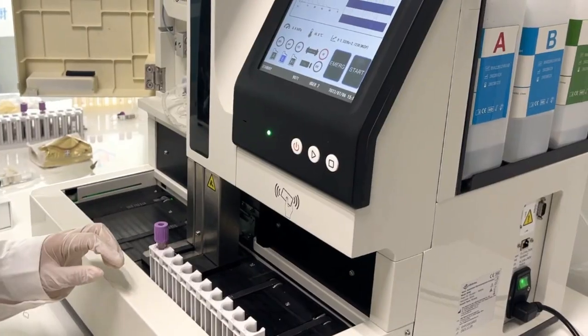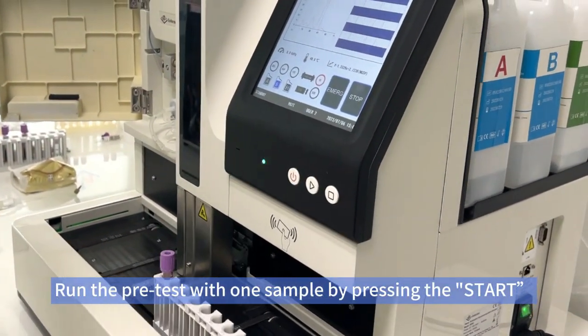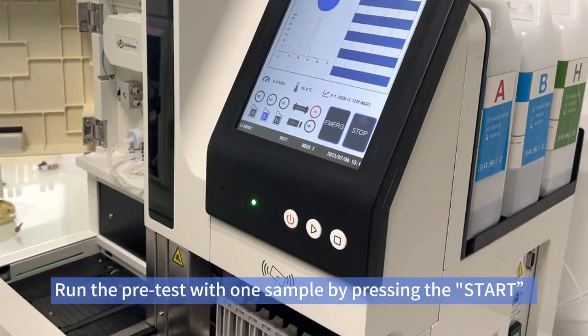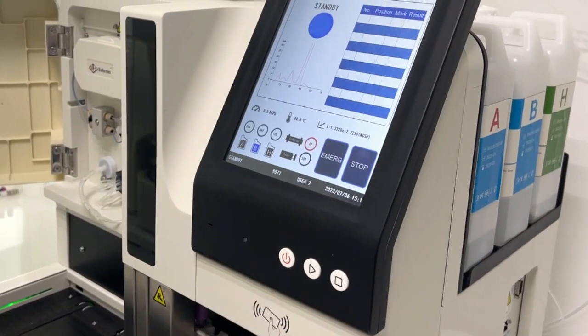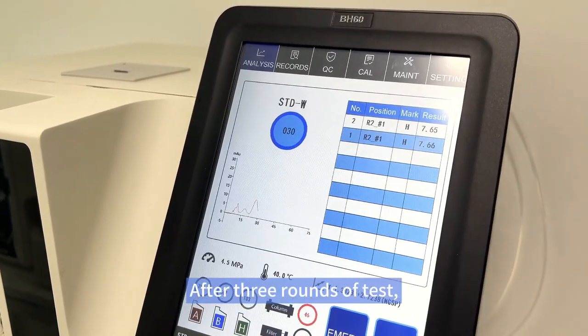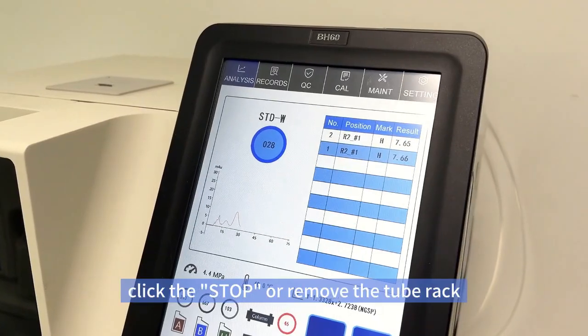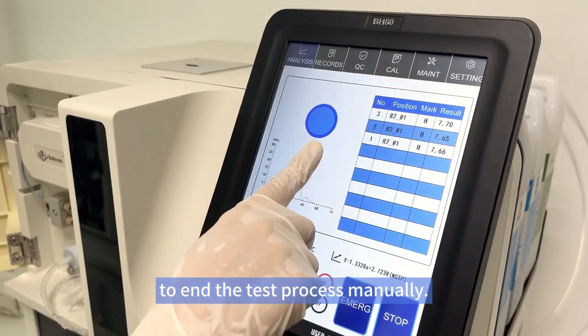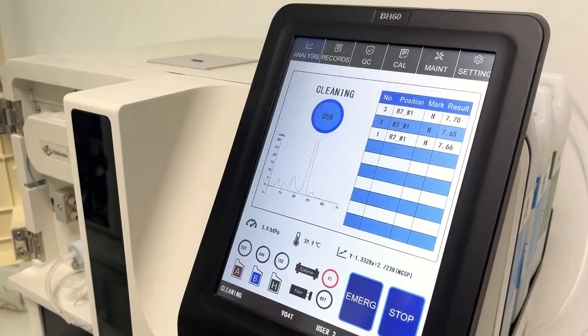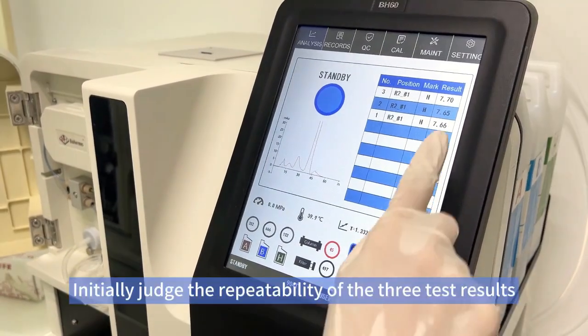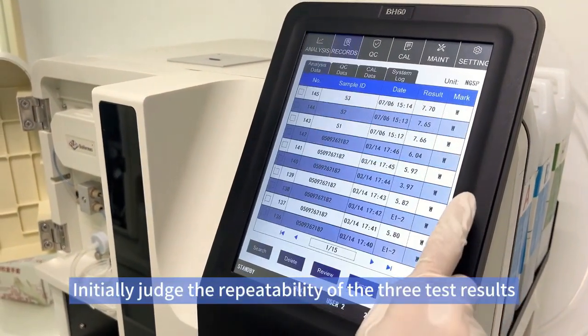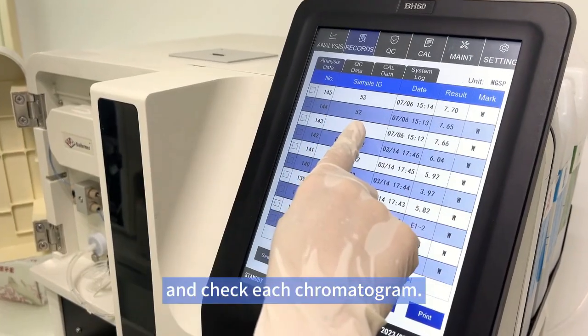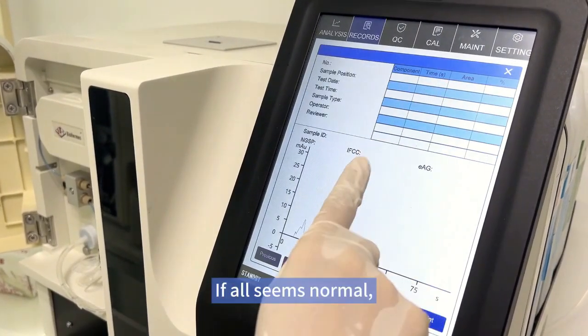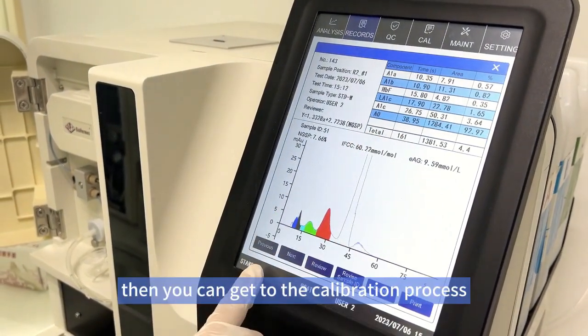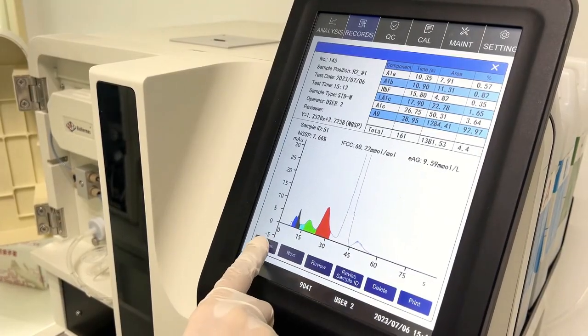Pre-test. Run the pre-test with one sample by pressing the Start under the Analysis interface. After 3 rounds of test, click the Stop or remove the tube rack to end the test process manually. Initially judge the repeatability of the 3 test results and check each chromatogram. If all seems normal, then you can get to the calibration process.